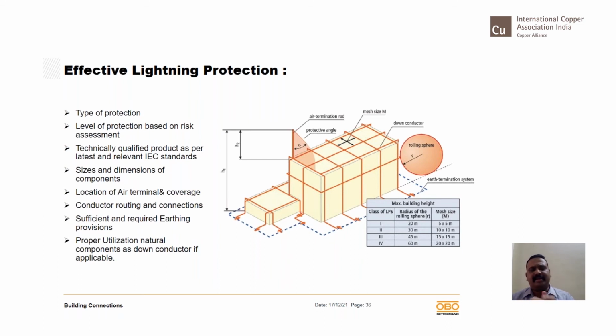Sufficient and required earthing is to be provided. Wherever there are down conductors, there should be earth locations and earthing should be properly provided. And proper utilization of natural components. As I explained in the previous case study, if you use natural components like rebar, handrails, facade, or beams, all of these have to be properly connected, and you must ensure that equipotentialization is done.